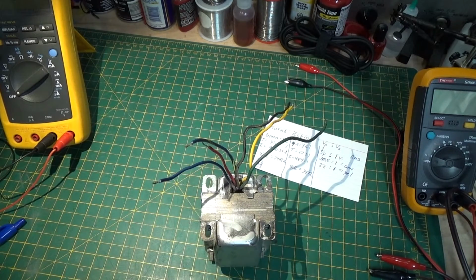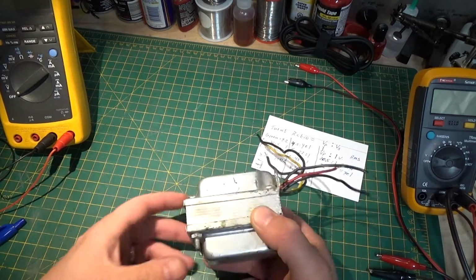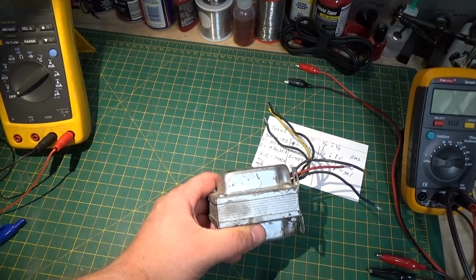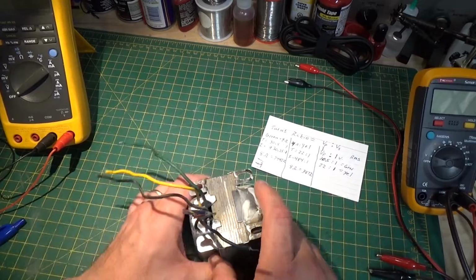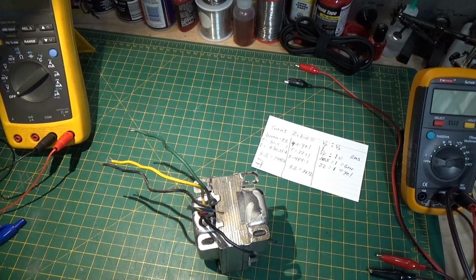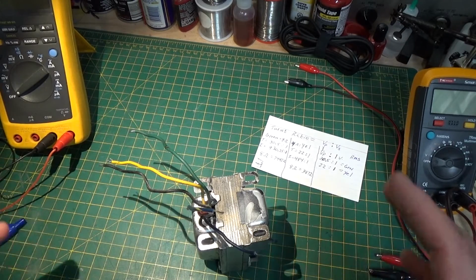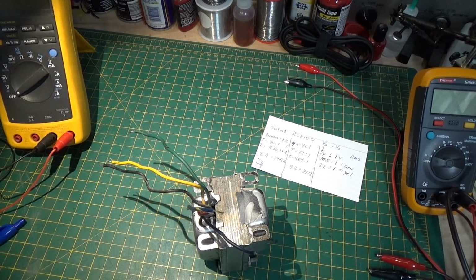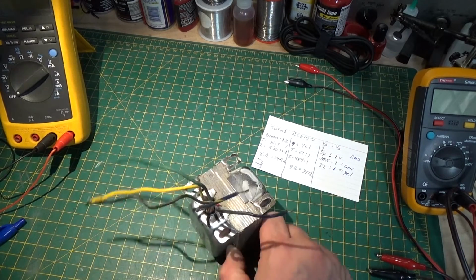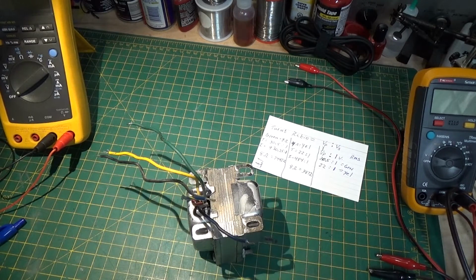So some of the more expensive transformers use a more expensive type of core material. They'll also use larger amounts of core material. The bigger the iron, the more magnetism you can create, and the better the transformer will perform, to a certain point. Transformers with little iron that are tiny will lose their magnetism, they'll saturate more quickly. They call that saturation.